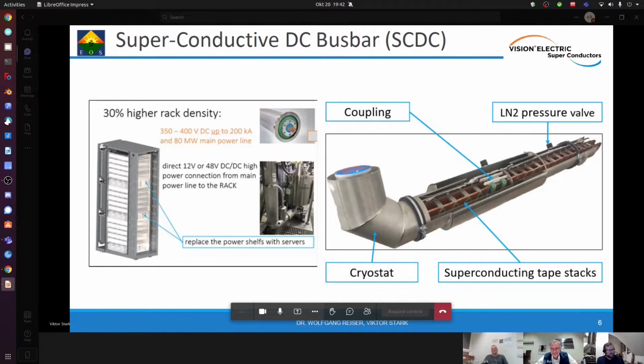So to explain, we see on the left side close to the rack the cryostat, and also a tap-off system, a cooling tap-off system. What is needed to go from superconducting temperatures, about minus 200 degrees Celsius, 77 Kelvin, to regular temperature? The tap-off box, you can also say, is a current lead. May I explain it a little later on the next slide? Yeah sure, okay sure.